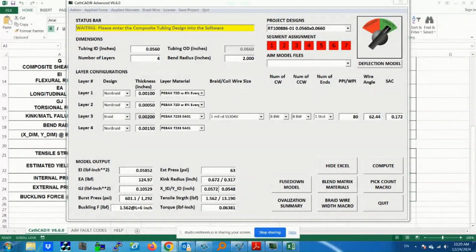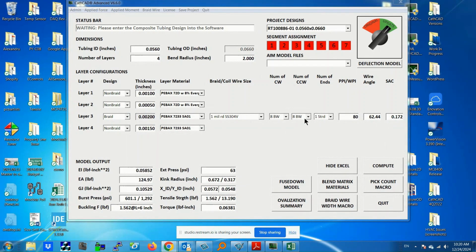If we want to go down that path, you'll see how easy that is. So I'm going to share my screen again. So again, here we are looking at our design, and now we want to determine in this design, do I have the right braid density? The way of doing that, typically once a braid wire has been selected, is to actually look and maybe change the picks per inch. So that's this parameter right here.